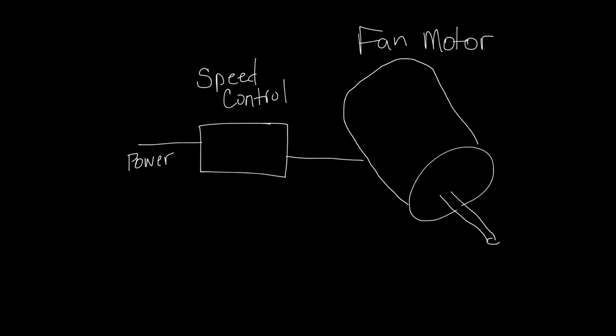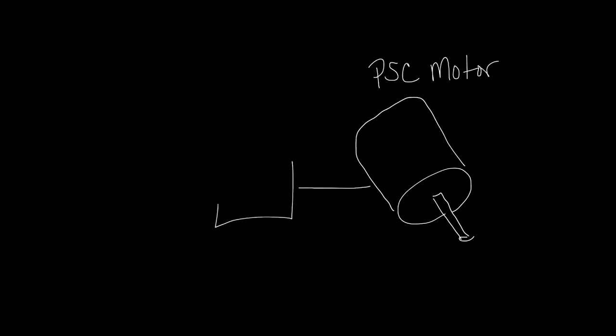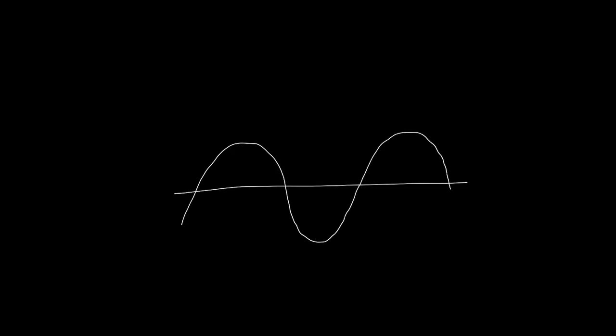There are two types of fan motors used in terminal units. Permanent split capacitor, or PSC motors, typically use a silicon-controlled rectifier, or SCR, speed control in order to make this adjustment. SCR is the proper technical name for what most people would call a dimmer switch. These devices basically take a nice smooth AC sine wave power and chop and notch it in order to reduce the usable power supplied to the motor.